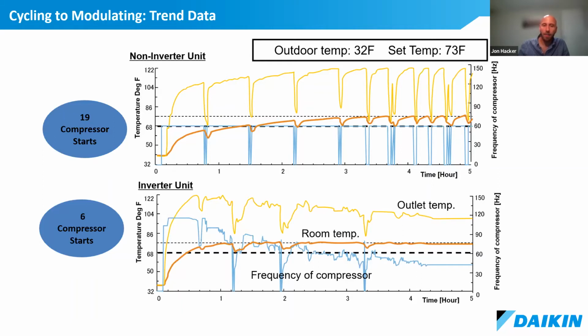What we're showing on the bottom half of this slide is that the inverter unit is a totally different operation. I think it's very obvious it looks different. And we're going to focus on the blue line first again. When you initially power that unit on, you'll see that the frequency is spinning well above 60 hertz. It's actually going up to close to 120 hertz, right? And then as the orange line approaches the set point, the unit begins to modulate its capacity and delivery of heat to find the optimal operating condition for the system. So it begins modulating the frequency, and as it's doing that, it starts and stops a little bit. But ultimately, after 2 or 3 hours, what you'll notice is it really just starts making small adjustments to maintain comfort. And what you'll see on the inverter unit is that orange line is basically fixed on that set point. Doesn't really deviate a whole bunch from it.